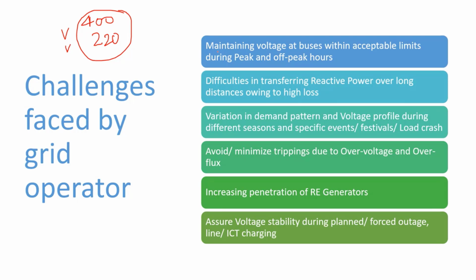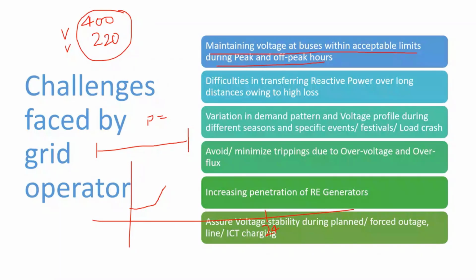So what the operator has to do is maintain the voltage at the bus within the acceptable limit during peak and off-peak hours. Let us say this is the power being transferred over a 24-hour duration. In the morning, the active demand is less, so it is like this. As soon as you move into the daytime, the power flow on this transmission line will increase. Then at the evening peak it increases again, and at night it reduces again. So this is the power flow on this transmission line throughout the day.